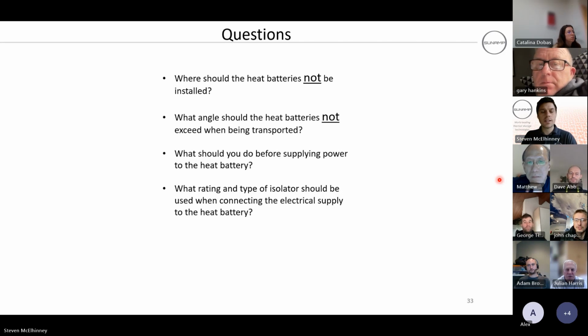Reduce capacity because of their external loss, isn't it? Yeah, heat losses, basically. Heat losses will be high. What angle should the heat batteries not exceed when being transported? 45 degrees. Spot on. What should you do before supplying power to the heat battery? Make sure there's water in it. Yeah.